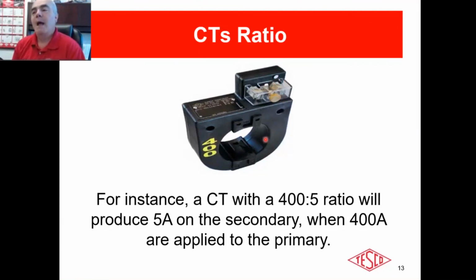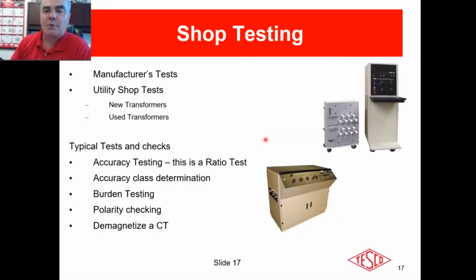Remember, it only cares about one primary and the number of turns. All right. However, if I have a whole batch of transformers that were marked incorrectly and I didn't reject them, then if I ever used 1 or 2 of them with a transformer or 2 transformers from another batch, I would have a problem. So again, it happens very rarely, but I've actually seen it 3 times now. But I get to see probably more instrument transformers than most folks. So it's very rare, but it does happen. So checking the polarity is also important.